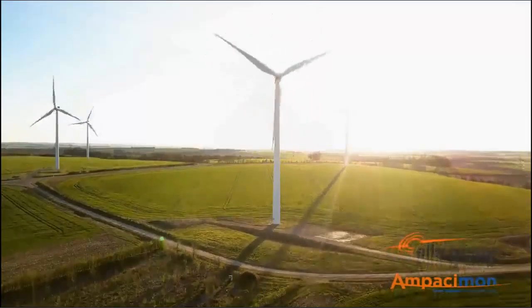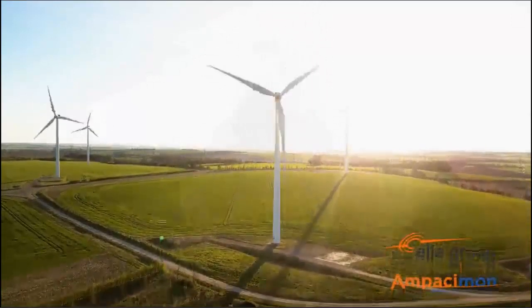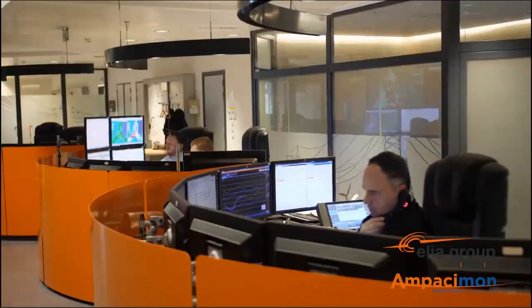There are two big use cases for ELIA using Ampacity. First one is in real time. Near the coast, we have a lot of wind farms connected, and without Ampacity before, if there is congestions, the only solution is to reduce or to curtail wind. In this case, once you install Ampacity, there is less redispatching you have to perform. And it's very interesting to see that there's a correlation between Ampacity and wind in feed. So the days when there's a lot of wind and higher congestion are also the days where there is more Ampacity given thanks to Ampacimon.